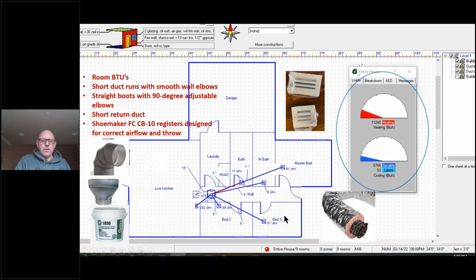So every single load in the room is figured out. It does our pipe sizing, so every single pipe size is figured out. So we have this perfect airflow running through these registers. We want to see like 400 to 600 CFM per ton running through these. It has to run at this speed. If it runs slower, we have this conductive loss. So we have this real big, gigantic ductwork. We're getting really good airflow, but with big ductwork it's just pulling the heat from the attic. This, as I didn't say, is in the attic, so you have all of this going against you. So if you can make this whole system right, make these runs short, and use the right size ductwork, there's a huge amount of savings here.